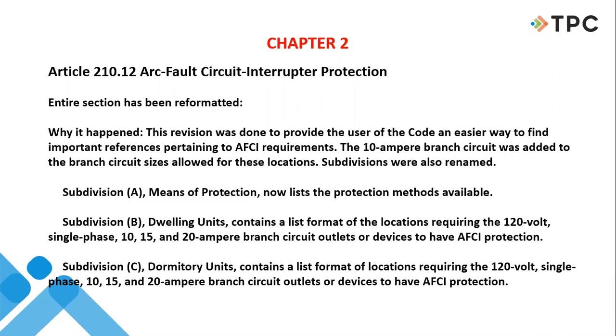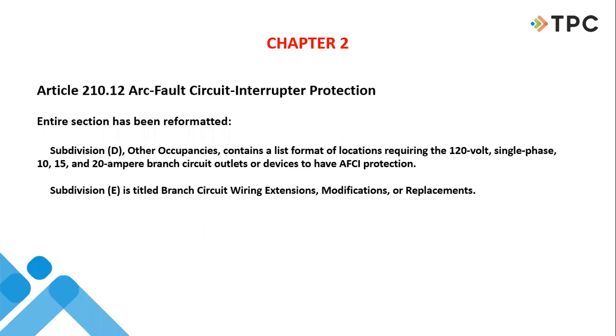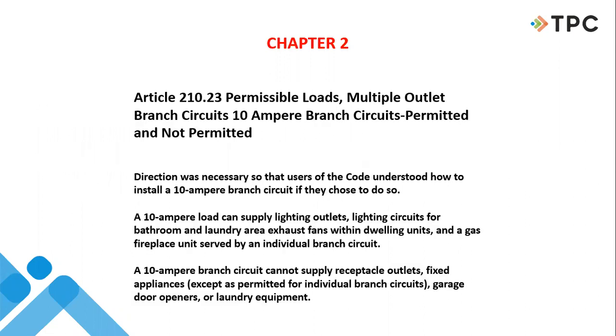The subdivisions are now, subdivision A identifies means of protection. It lists all the protection methods available. Subdivision B for dwelling units, nice list format of all the locations requiring AFCI protection, both 10, 15, and 20 amp circuit outlets. Subdivision C deals with dormitory units, same concerns. And then subdivision D, they branch out into other occupancies. And then last but not least, they get into branch circuit wiring, extensions, modifications, or replacements. Bringing old wiring up to modern levels. How far out do we extend the latest and greatest code mandates? That's what subdivision E is going to be concerned with.